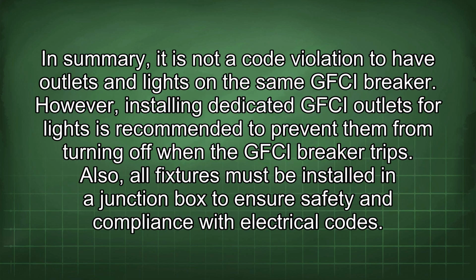In summary, it is not a code violation to have outlets and lights on the same GFCI breaker. However, installing dedicated GFCI outlets for lights is recommended to prevent them from turning off when the GFCI breaker trips. Also, all fixtures must be installed in a junction box to ensure safety and compliance with electrical codes.